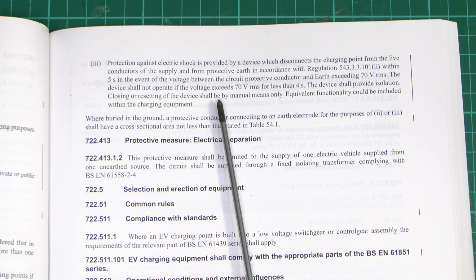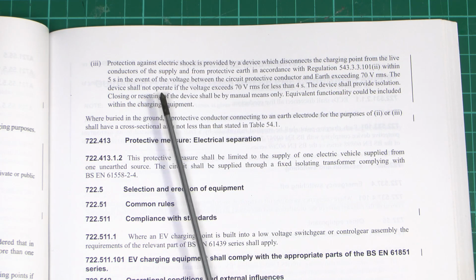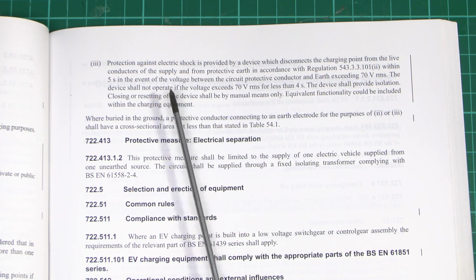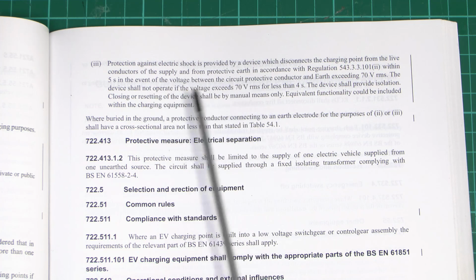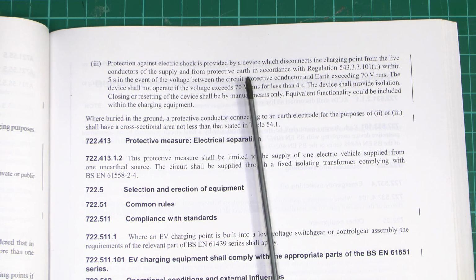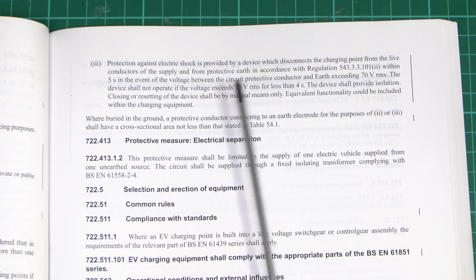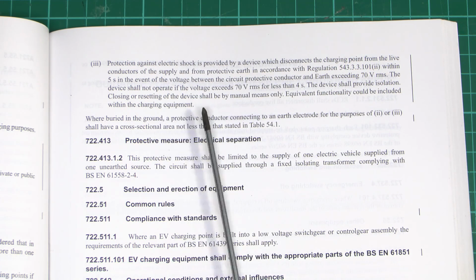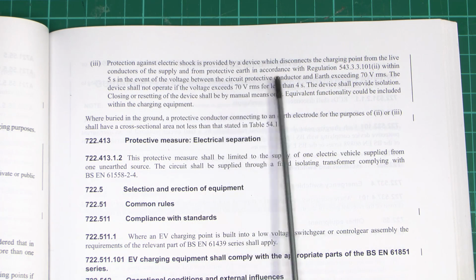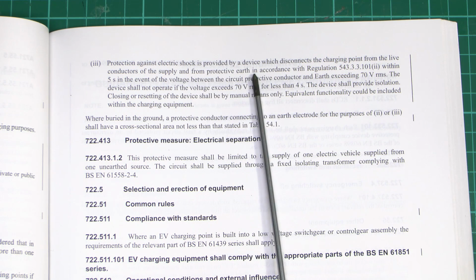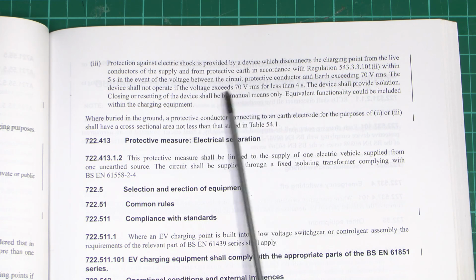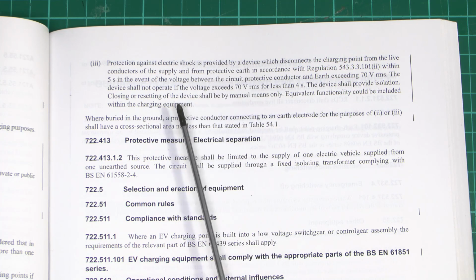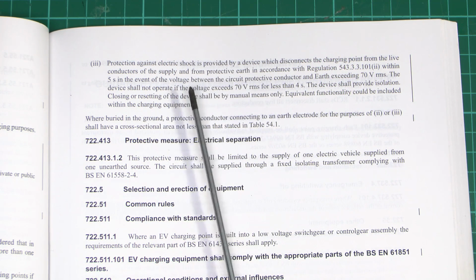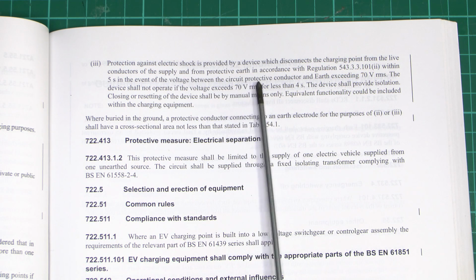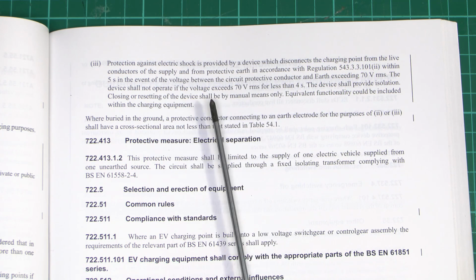So this is a device which monitors the actual voltage between the protective conductor, which is the one that's provided by the supplier, and the actual real earth, as in it's going to have its own electrode or connection to that. If the voltage exceeds its 70 volts, it's going to disconnect the line, the neutral, and, most importantly, the protective conductor as well. And this is to prevent dangerous voltages appearing there. So again, if that combined conductor was broken, any voltage that shows up on the protective conductor is going to be disconnected, and it won't present a hazard to those persons using the equipment.